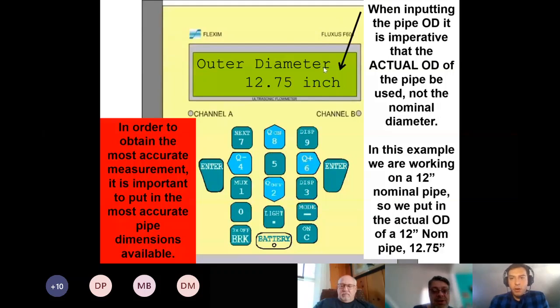And then it'll bring you to this menu for outer diameter. The big and most important thing here is that you are actually measuring your outer diameter, your actual outer diameter, and not the nominal diameter. So we have a pipe lookup chart. You folks can reach out if you don't have it. It should come with most meters, though, a printout of it, and it's a lookup chart to determine what the actual OD is depending on the pipe material.